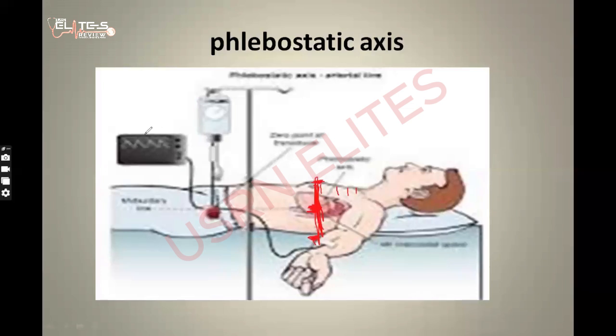This is a screen or a monitor for invasive monitoring. It's like a normal cardiac monitor, but some cardiac monitors can monitor invasive procedures too. Some cannot, but in this case, you have to get one that can be used to monitor invasive procedures. This is just a normal saline fluid. You can see a pressure bag wrapped around it, like an infusion bag pump, because you have to create pressure here. So you have a giving set connected from here to the transducer.